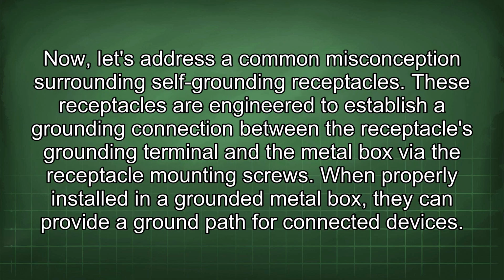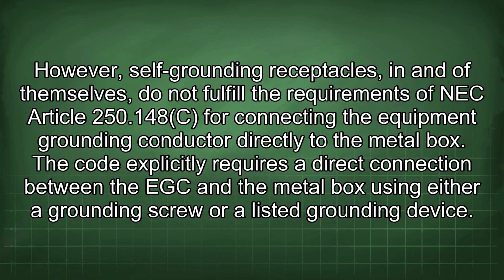Now, let's address a common misconception surrounding self-grounding receptacles. These receptacles are engineered to establish a grounding connection between the receptacle's grounding terminal and the metal box via the receptacle mounting screws. When properly installed in a grounded metal box, they can provide a ground path for connected devices. However, self-grounding receptacles, in and of themselves, do not fulfill the requirements of NEC Article 250.148c for connecting the equipment grounding conductor directly to the metal box.